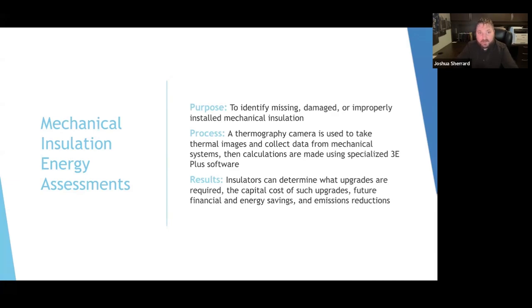It's insulation that has been removed for maintenance purposes and didn't get reinstalled. Using thermography, we're able to isolate the energy loss at that point of contact, calculate what that's costing the facility, and put together a cost-effective approach to their overall mechanical insulation system maintenance.